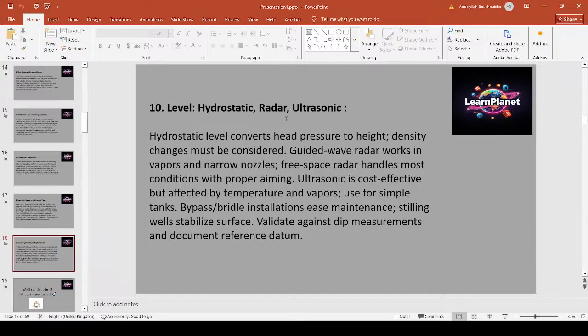Level: hydrostatic, radar, ultrasonic. Hydrostatic level converts head pressure to height. Density changes must be considered. A guided wave radar works in vapors and narrow nozzles. Free space radar handles most conditions with proper aiming. Ultrasonic is cost effective but affected by temperature and vapors. Used for simple tanks, with bypass chambers and stilling wells to ease maintenance and stabilize the surface. Validate against dip measurements and document reference data.